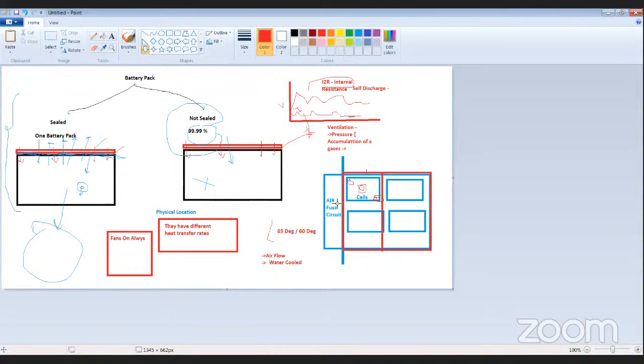In terms of airflow, one recommendation: if you are using an airflow circuit, avoid having airflow in this direction. This compartment is kept separate for fuses, because these are hot components carrying very high current, switching and everything, so components can heat up. Try to avoid air flowing from this direction to there. You can have opposite flows instead, air coming from here and going there.